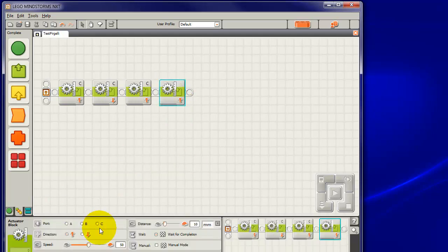I originally wanted it to come backwards, C, come backwards at 25%, but when I put it at 25% and made it at 80, we got absolutely nothing. It just sat there and didn't move. The internal friction inside the Firgelli actuator is such that on the particular one I'm testing, I needed at least 35% before it would even move. That was the minimum amount of power I could have. So anything below 35, it just sat there and didn't move.